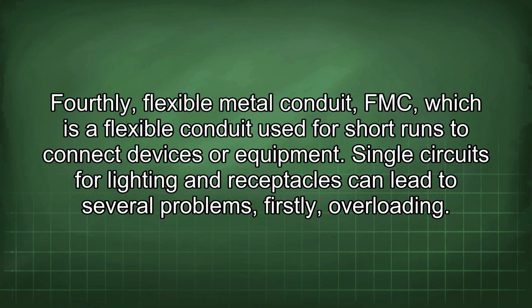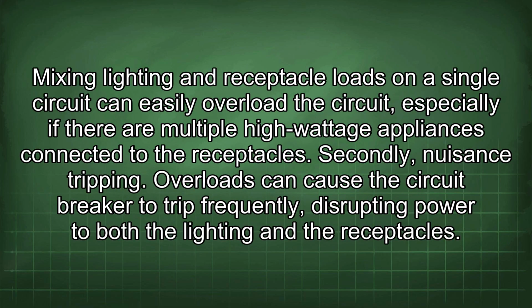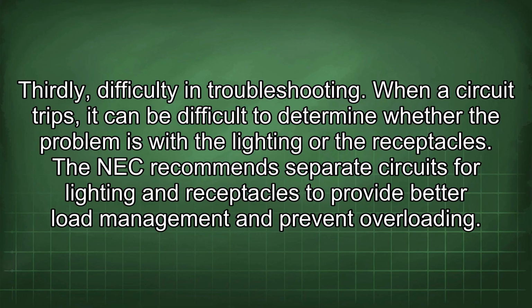Single circuits for lighting and receptacles can lead to several problems. Firstly, overloading. Mixing lighting and receptacle loads on a single circuit can easily overload the circuit, especially if there are multiple high-wattage appliances connected to the receptacles. Secondly, nuisance tripping. Overloads can cause the circuit breaker to trip frequently, disrupting power to both the lighting and the receptacles. Thirdly, difficulty in troubleshooting. When a circuit trips, it can be difficult to determine whether the problem is with the lighting or the receptacles. The NEC recommends separate circuits for lighting and receptacles to provide better load management and prevent overloading.